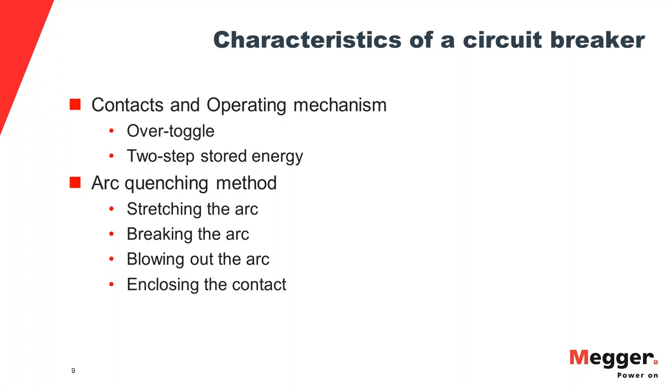move the handle. Then there is the two-step stored energy mechanism, which is used in low voltage power circuit breakers, where there are separate springs for opening and closing of the breaker. So you can actually charge the spring for closing a breaker even before it has opened. What that does is give a reclosing ability to the breaker. So if the breaker opens in the case of a fault, it can be immediately reclosed remotely.